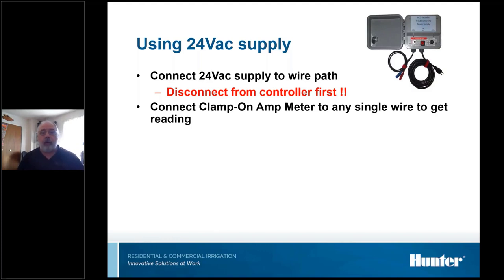When we do this, you only check one of the wires, and it doesn't matter red or blue. It really makes no difference at all. The current should be the same on both wires. If the current was different on one of the wires than the other, it's telling you you got a nick in the wire and it's bleeding some voltage off the ground. Probably not what's causing your main problem, but it's telling you got something wrong. So when we do this, we're going to see quite a bit of variation in the milliamp reading for the current draw for decoders.